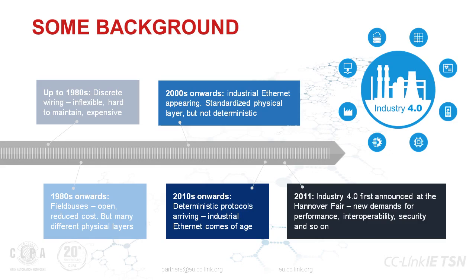Starting in the 1980s and onwards, we saw the introduction of field buses. They improved the situation because they allowed you to connect different devices together in a system. Rather than using inflexible discrete wiring, you could now connect everything together using a single cable, making things a lot more flexible and easier to install, maintain, and design. But they still weren't perfect — one of the main drawbacks was that individual field buses were not compatible with each other. If you had field bus A and wanted to use those devices with field bus B, that generally wasn't possible due to different physical layers and lack of interoperability.